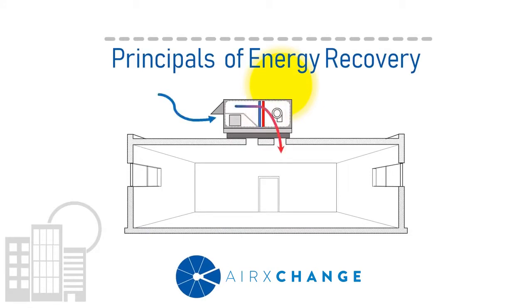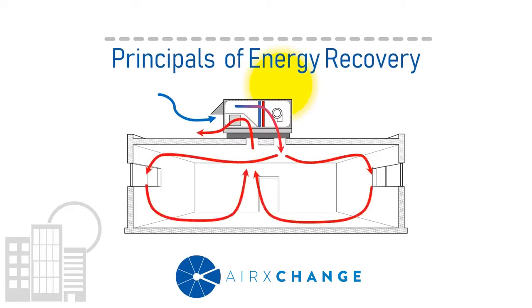the outside air comes into the unit and is heated or cooled by the primary conditioning element to a point that is suitable to be delivered to the space. The outdoor air dilutes the space air with fresh air, and the stale air is then exhausted back through the unit. The exhaust air contains energy that can be used to perform work prior to it being lost to atmosphere.